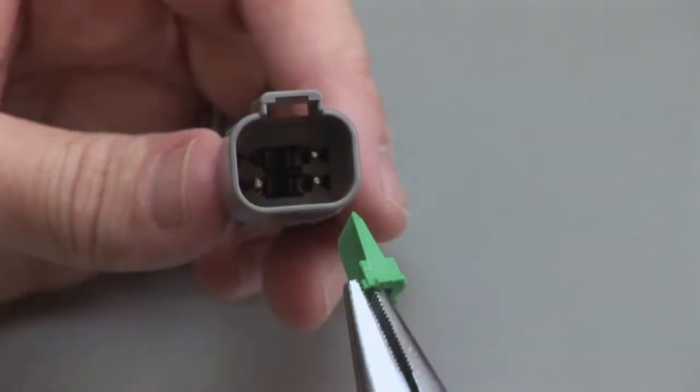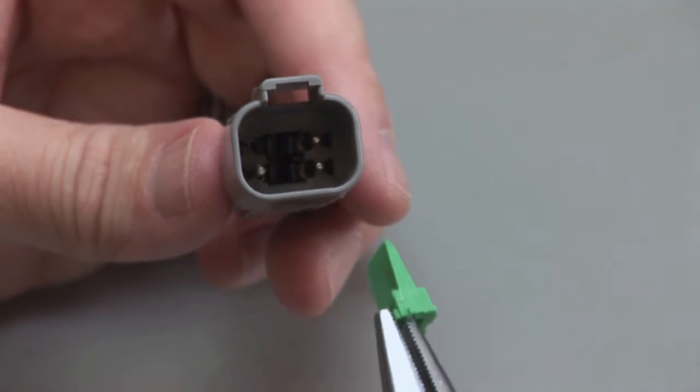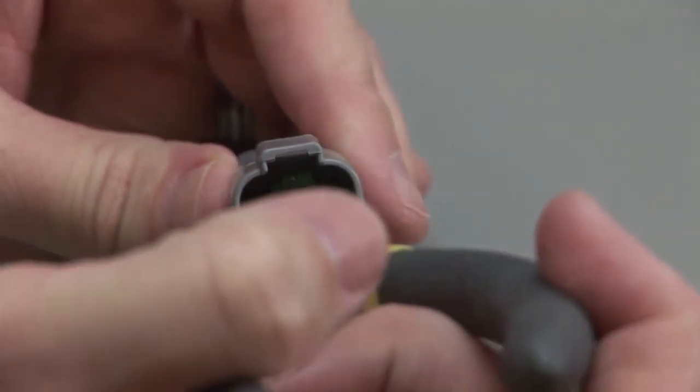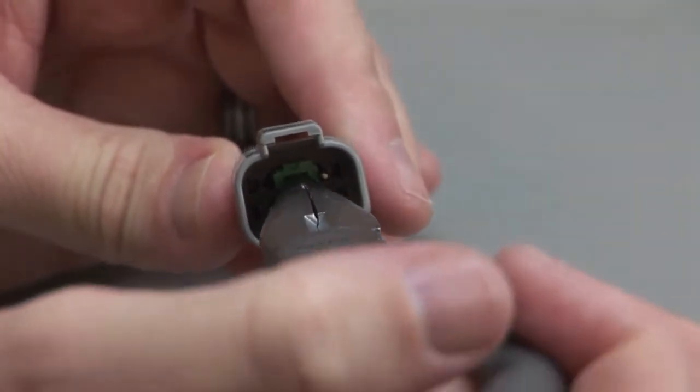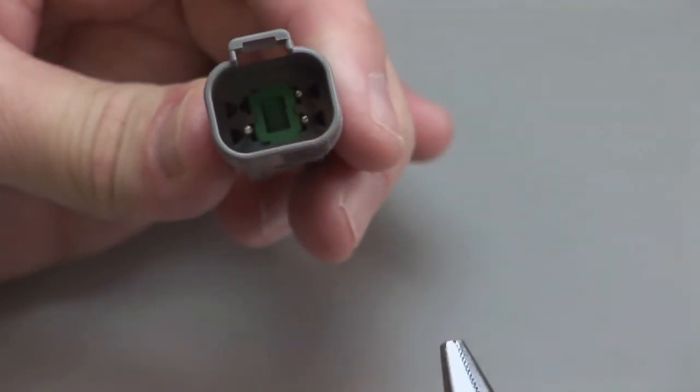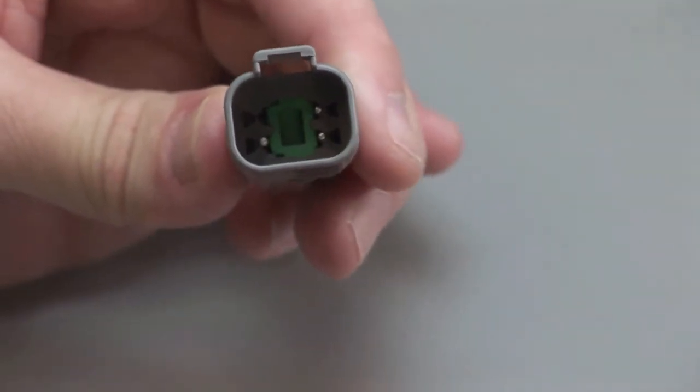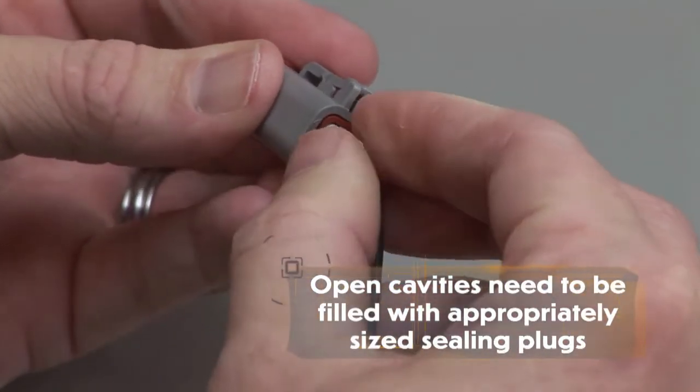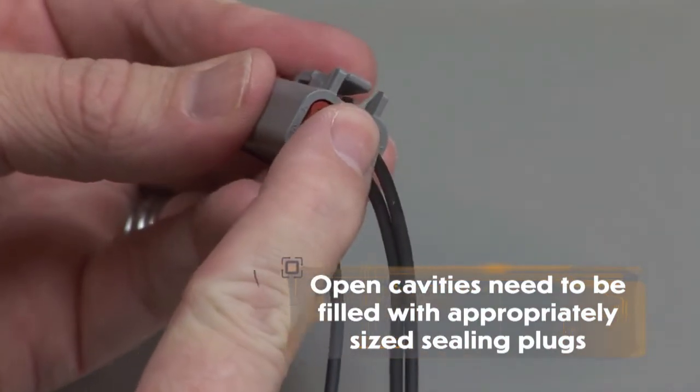To insert the wedge lock in the receptacle housing, select the appropriate wedge lock. Carefully align the wedge lock between the locking fingers in the interface of the receptacle. Apply downward pressure until a click is heard and felt. Please note that if you have open cavities, they will need to be filled with appropriately sized sealing plugs.